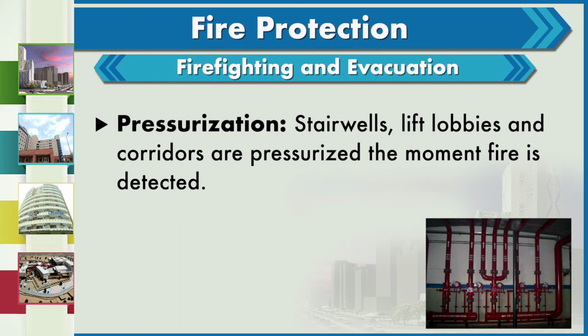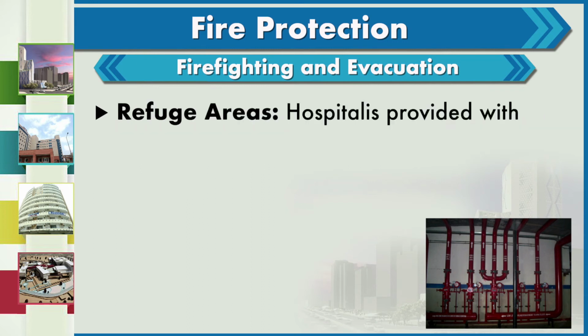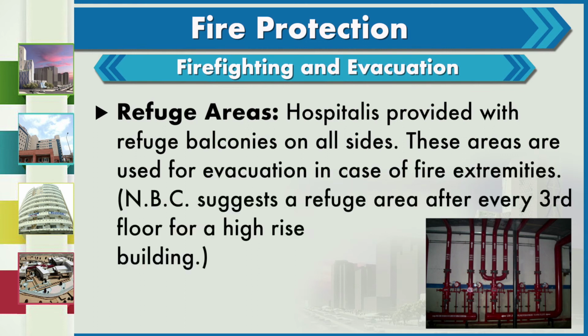They have to be pressurized at the time of fire. So, pressurization shafts are designed next to each staircase and lift lobby. Refuge areas. Now we provide refuge areas, which are like large balconies on all sides, so that people who cannot be immediately rescued out of the building can stay in that refuge area for some time. NBC suggests a refuge area after every 3 floors in a high-rise building.